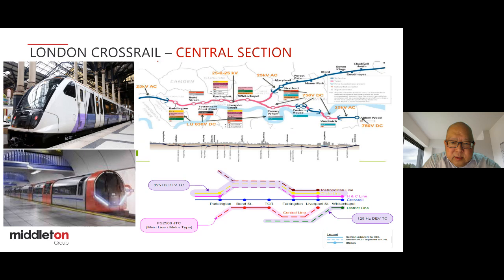Also, there are so many DC London Underground lines running in parallel to the Crossrail alignment, and London Underground would not accept any 25 kV system apart from auto-transformer systems, because only then can we pull back our own 50 Hz leakage current. Any other system, like rail return, would have been flowing in their infrastructure and returning via their running rail and their tunnel, which is also bonded to their rails as well.